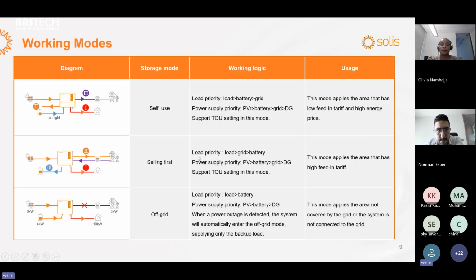Okay, for the working mode, we have 3 working modes. One is self-use, one is selling first, one is off-grid. For the self-use mode, we can define it by the working logic for the load priority. We supply the load first, then the battery is charged, and if there is still surplus power, it will feed into the grid.